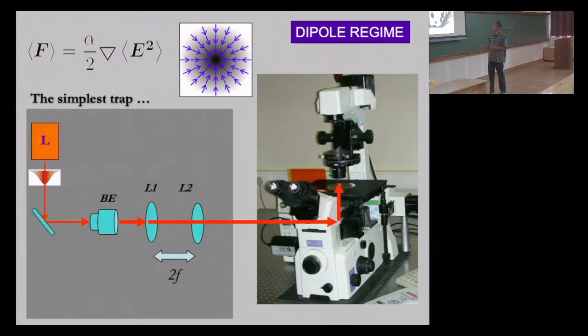Now, for optical tweezers, the main reason why you do this is because the laser beam that is coming in is below eye level. If I had an upright microscope, the laser beam would be coming in here, that would be at your eye level. That's extremely dangerous, because this laser is infrared, you will actually not even see it. So you will not know, but you will go blind if it goes to your eyes. So therefore, one has to be a little careful.